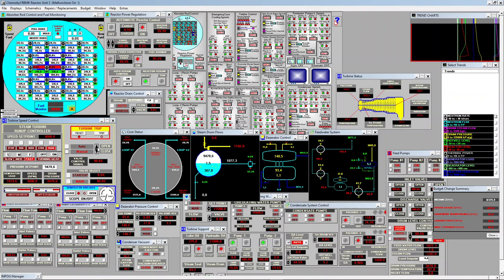Okay, let's increase a bit more the opening of the valve control signal. And you see, we already decrease the pressure to 9.3 megapascal. So what's the minimum? I don't know exactly, but I think it's around 7.5 megapascal. Below that value, we'll get an alarm of low steam temperature.